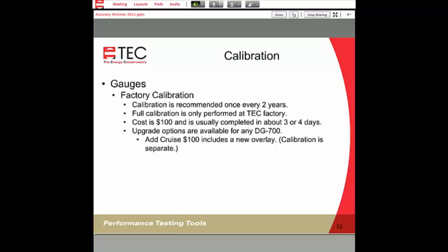So that means that from the day it leaves us and we've calibrated it, it will still maintain its accuracy, barring any severe service, over time, from now till 2 years from now, 24 months from now, it's still going to read within plus or minus 1%.